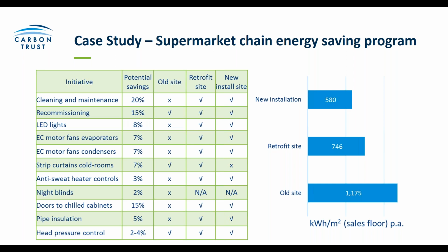You can see that the old sites that didn't have many initiatives put into them maintained around 1,175 kilowatt hours per meter squared. Where they were able to build a brand new installation, this of course had the most impact on energy savings. They were able to implement all the most up-to-date equipment and best practice available, and bring that energy use right down. Where they had existing sites that couldn't be knocked down and rebuilt, they were able to retrofit. Even just by retrofitting and introducing a good cleaning schedule, things like night blinds, but specifically doors on chill cabinets, probably the most effective, they were able to bring their existing energy use right down. So this gives you an indication of what can be achieved by retrofitting.